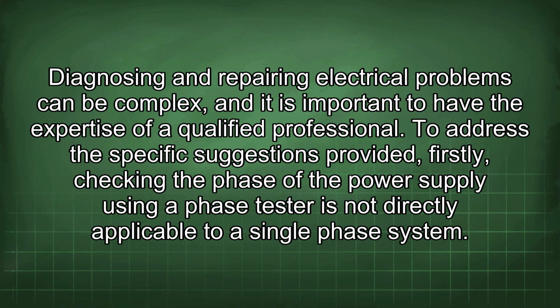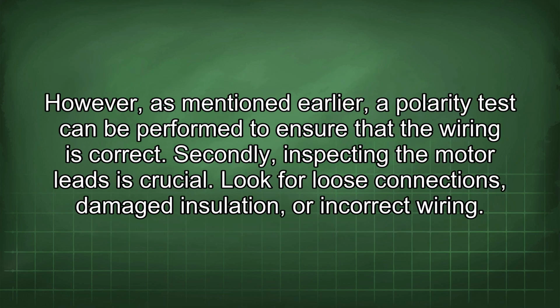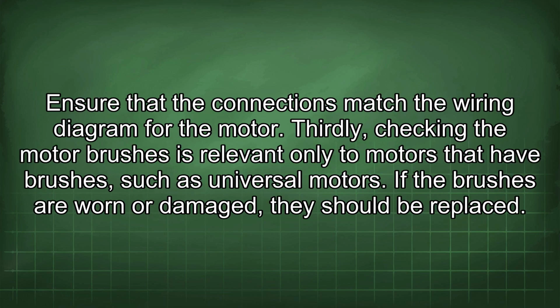To address the specific suggestions provided, firstly, checking the phase of the power supply using a phase tester is not directly applicable to a single-phase system. However, as mentioned earlier, a polarity test can be performed to ensure that the wiring is correct. Secondly, inspecting the motor leads is crucial. Look for loose connections, damaged insulation, or incorrect wiring.